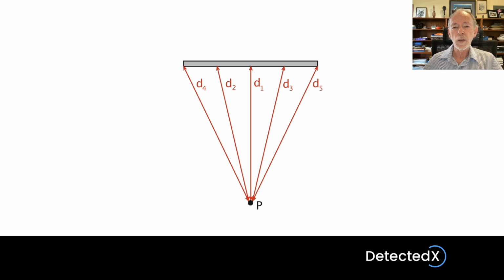The only way to deal with this, or at least the way in which ultrasound machines do deal with this, is to break the transducer up into a large number of little bits and transmit with each of those little bits at a slightly different time. And the timing is organized so that the pulses from each of those little pieces of the transducer will arrive at the point P at the same time. So that basically means we need to chop the transducer up into lots of little bits, and we refer to that as an array transducer. So that's the basis of how the ultrasound machine is going to focus, and we'll look at that in more detail in the next talk.